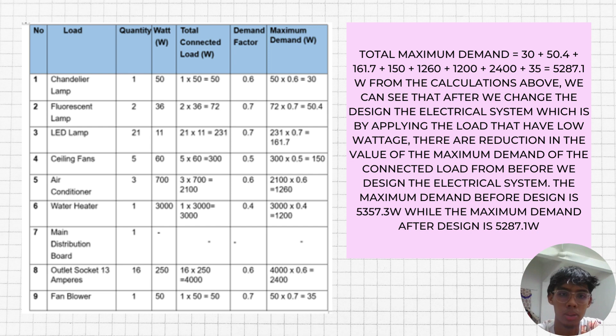Next, we will calculate the design current. Design current is one of the most important things in designing an electrical system, especially when choosing MCB, switch fuse, earth leakage, and ELCB (earth leakage circuit breaker). We use this formula: maximum demand over 240 times 0.85.